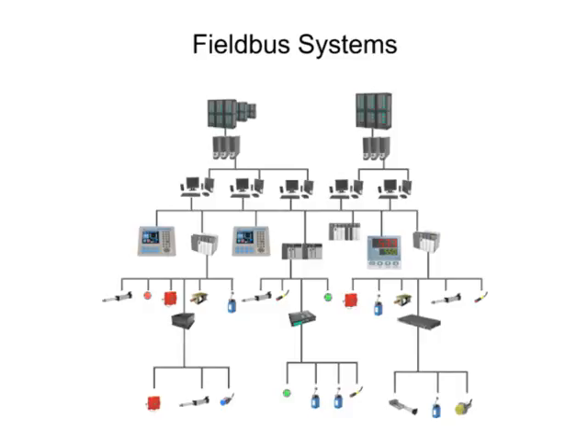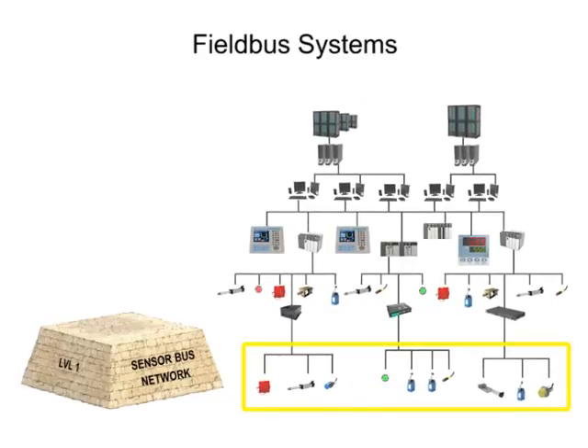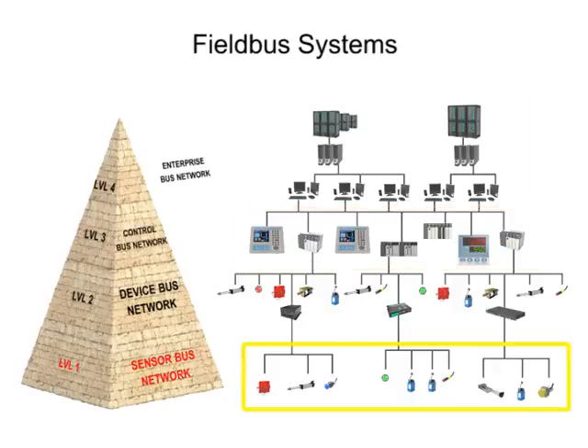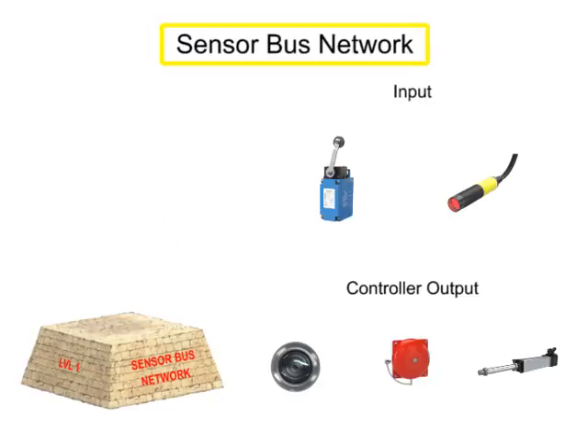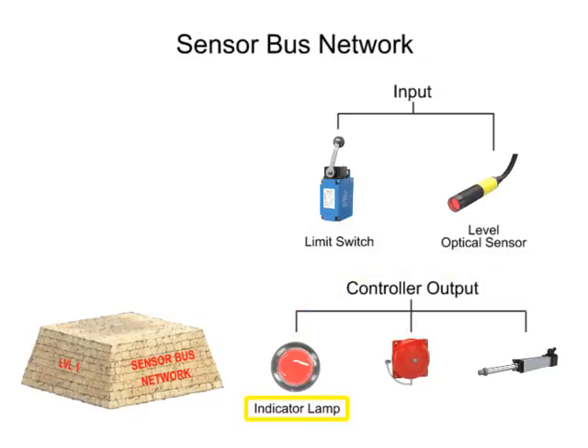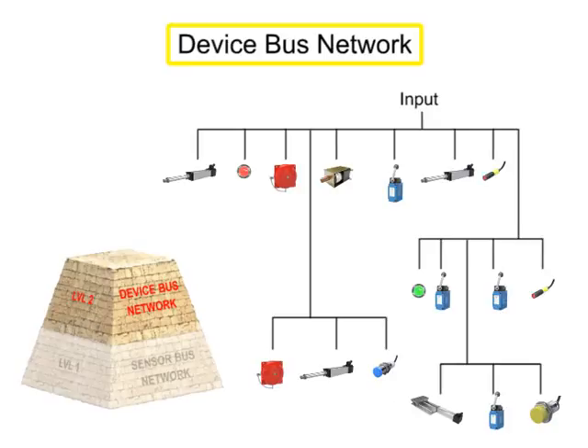Fieldbus industrial networks can be broken down into four levels, each with increasing levels of complexity. The most basic level is the sensorbus network. Sensorbus networks are the least complex of networks developed for industrial application. In these networks, multiple basic field devices like limit switches or level optical sensors are connected to one network cable. The sensorbus network is also capable of transmitting output signals from the controller over one cable to indicator lamps, alarms, or other actuator devices.